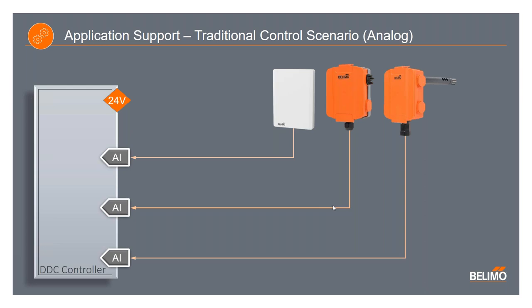On each of these points, the programmer of the DDC system needs to know some of the details on the sensor when programming and commissioning. For instance, with the pressure sensor, they would need to know the signal range such as 4 to 20 milliamp, the pressure range — perhaps it's a 0 to 10 inch water column sensor — and whether or not it's bidirectional. With that, they would apply an analog input configuration, set the scale range, and potentially convert it to another unit if needed.